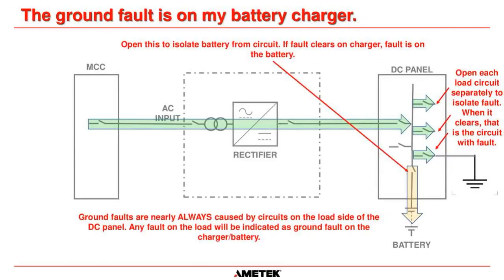But it's very rare that you're going to have a ground fault on your battery. The easiest way to check is that your ground fault detection system is either on your DC panel or in your charger. If you open your battery disconnect and the ground fault alarm clears, then yes, the ground fault is on your battery. But if you open the battery disconnect and the ground fault remains on your charger or DC panel, then it is not on the battery.